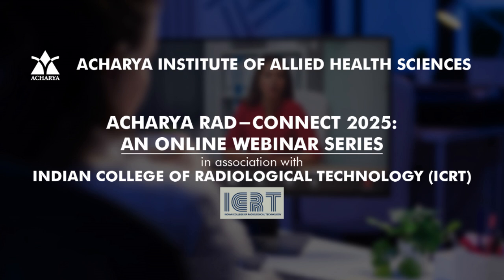Whether tube current modulation is used in low dose CT? Yes, without tube current modulation, low dose CT cannot be possible. And tube current modulation is not an option to deselect; it is present in each and every scan. You cannot deselect it. It can only fail if you have not selected the proper protocol. Like if a pediatric patient, a 1-year-old child, has come and you have selected the adult protocol for the scanning, then tube current modulation won't work. You have to manually select it. Or else usually the 3D dose modulation is automatically switched on for each and every scan.